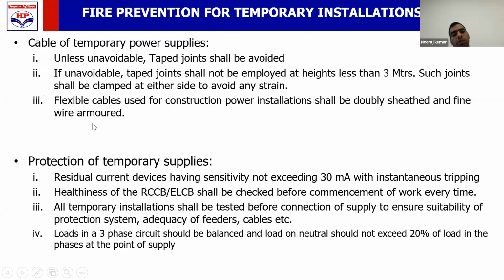Now, how do we protect our temporary supply and the people working on them? You should have a 30 milliampere earth leakage protection device. Those earth leakage protection devices should be checked every time before starting the work. आज चेक किया, 7 दिन तक काम करते जा रहे हैं, सर चेक किया था 1 वीक पहले, नहीं चलेगा. Every time you start the work, you should check the ELCB or RCCB, whatever earth leakage protection device is available.